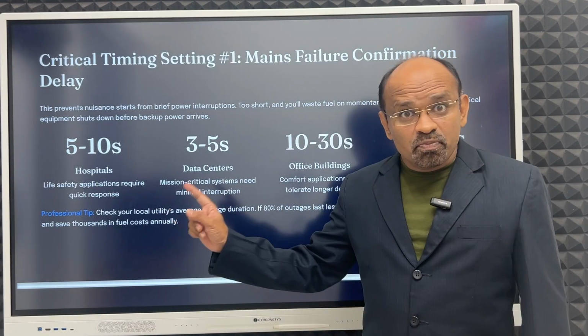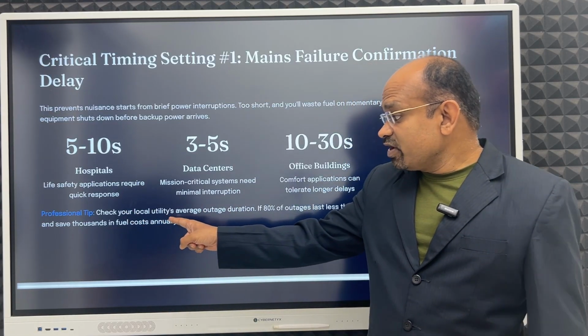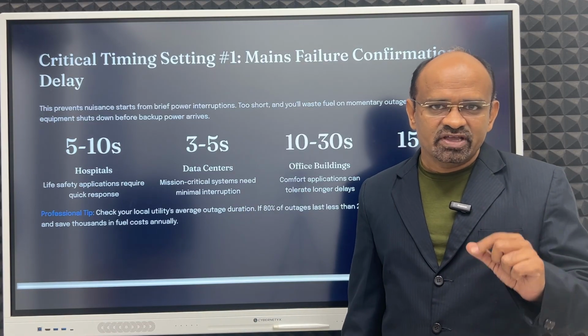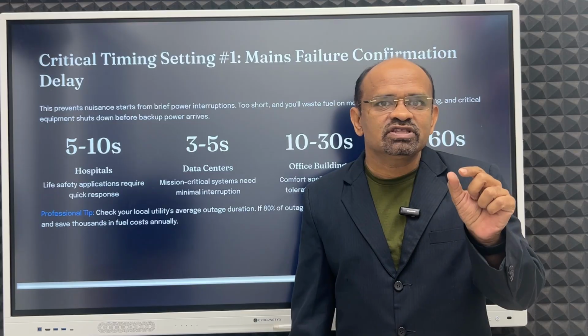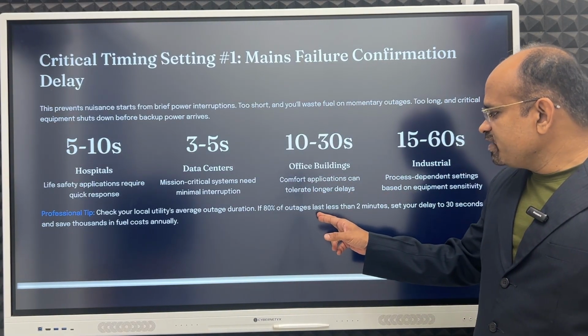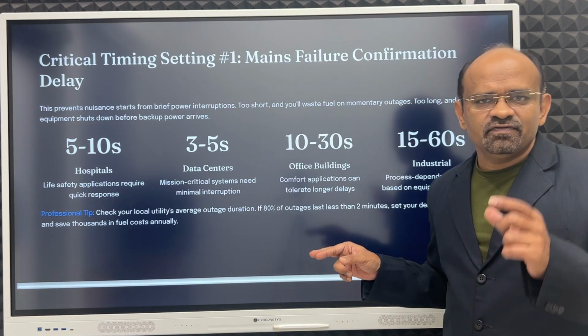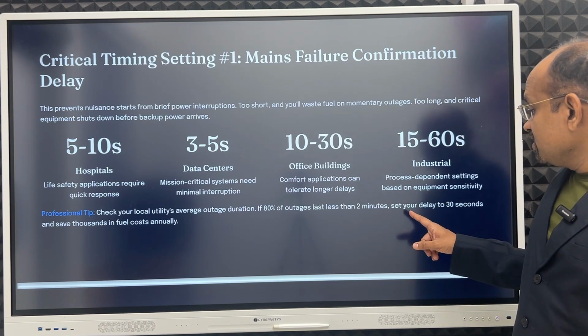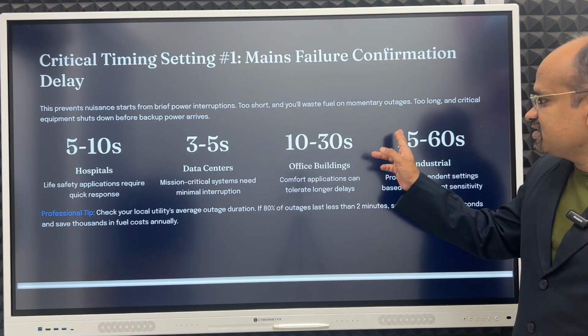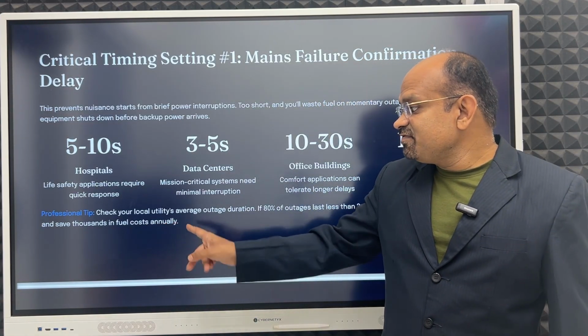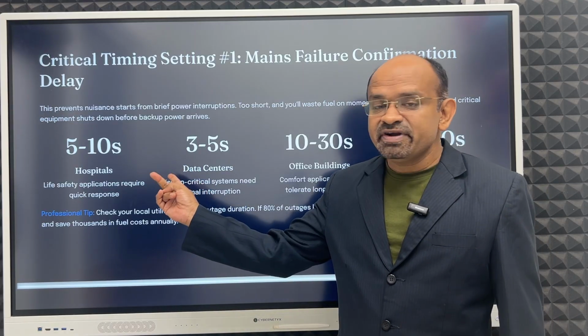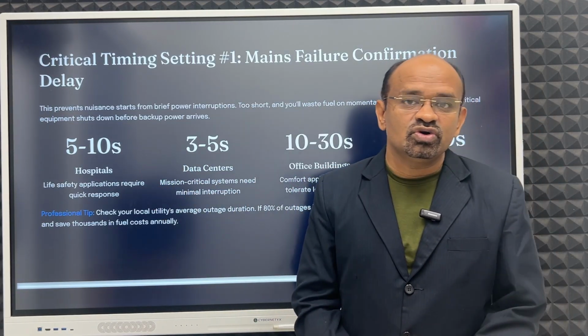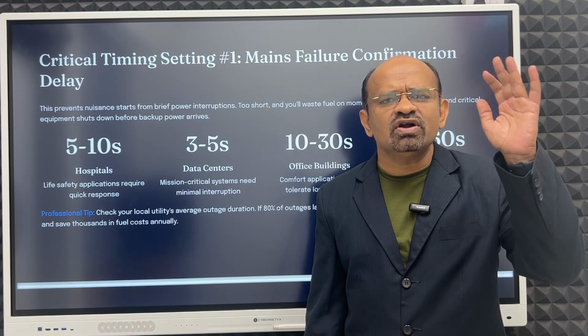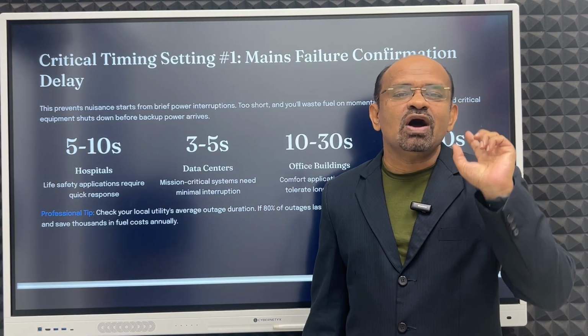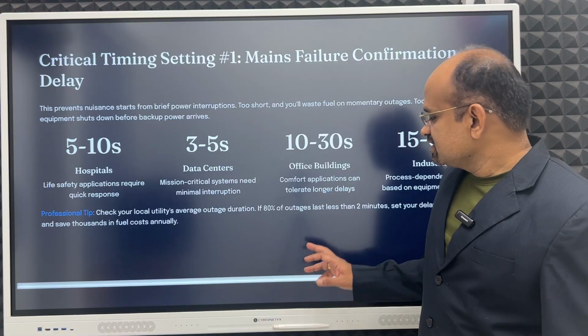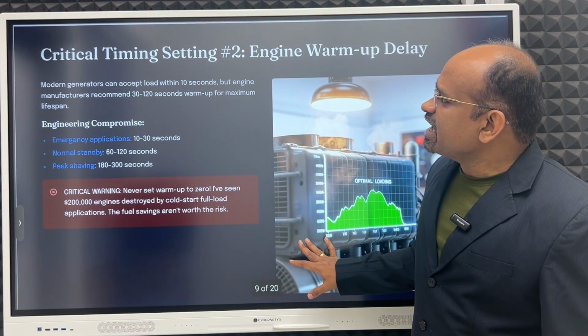Okay, now professional tip, just remember this tip. Check your local utility's average outage duration. Is it momentary, or does it take longer, more than 2 minutes, 5 minutes? We'll see. If 80% of the outages last less than 2 minutes and power comes back, then what to do? Set your delay to 30 seconds and save thousands in fuel cost annually. But don't do your experiment with these critical loads. This you can do, and you will save thousands in fuel, because it will not kick off the DG as soon as there is a small outage, 1 minute or even less than that, or 30 seconds we have seen.